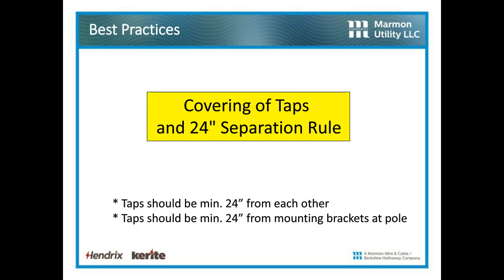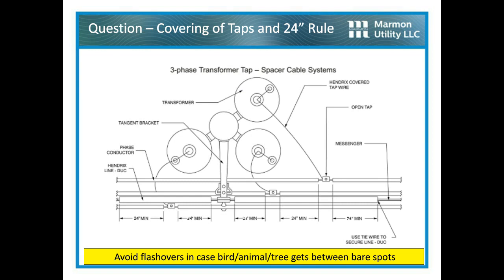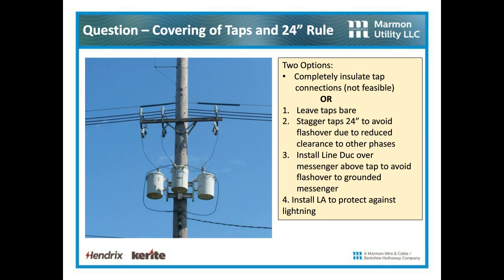Quick one is, well, how about the covering of taps and the 24-inch separation rule? This one's simple. Taps should be a minimum of 24 inches from each other, and a minimum of 24 inches from the mounting bracket. You can see in this drawing in the catalog that those taps are 24 inches from each other and 24 inches from the pole, or should I say the mounting bracket. And when I do that, I can either insulate that tap, no problem, or leave that tap bare. I might need to leave it bare since I'm using a stirrup, right? So I'm going to stagger the taps 24 inches, install Line Duc over the messenger, and install a lightning arrestor to protect against lightning. You've probably got an LA anyway because you've got a transformer there.